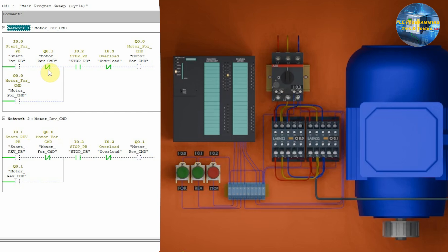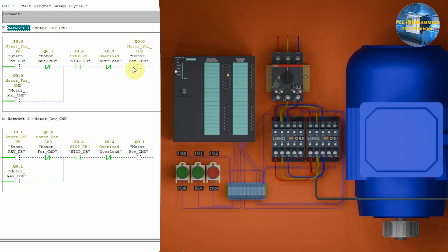this will turn on the motor forward command Q0.0. This Q0.0 output will be latched on through its own normally open contact Q0.0 through this path.